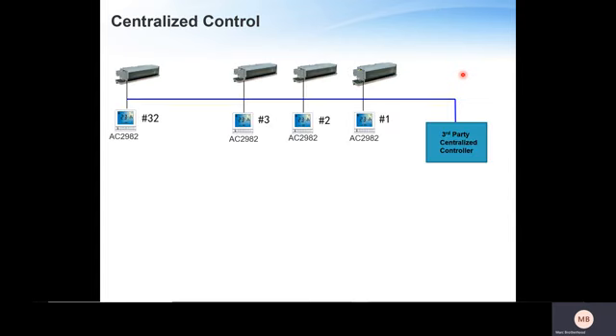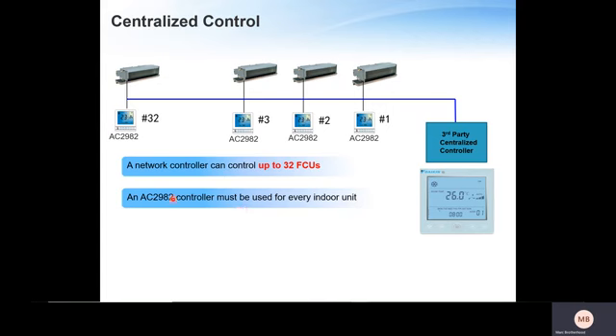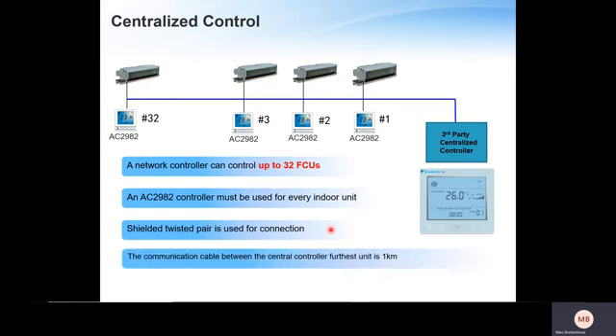If we want to go for centralized control, a third-party centralized controller, for example, a network controller, depending on what the third-party controllers can generally control up to 32 fan coil units. And very importantly, an AC2982 controller must be used for every indoor unit. That is because we daisy chain the RS485s. Shielded twisted pair used for connections. The communication cable between the central controller and the furthest unit can be up to 1 kilometer.